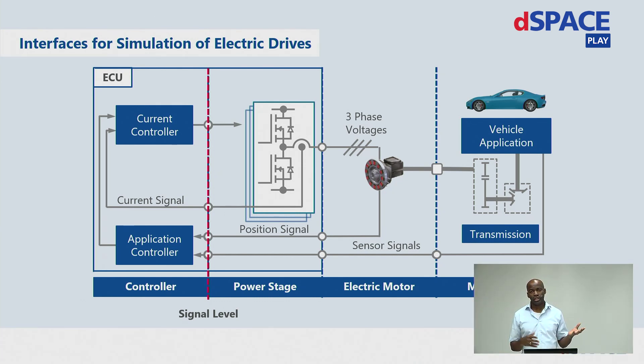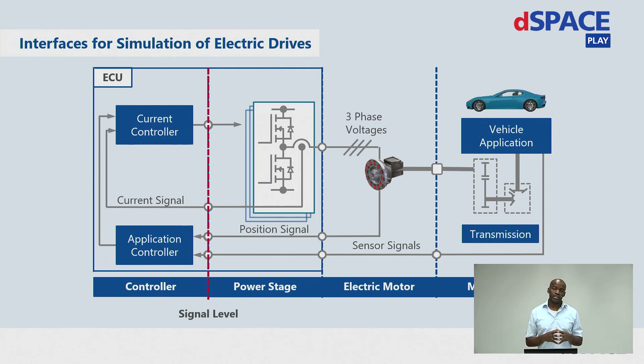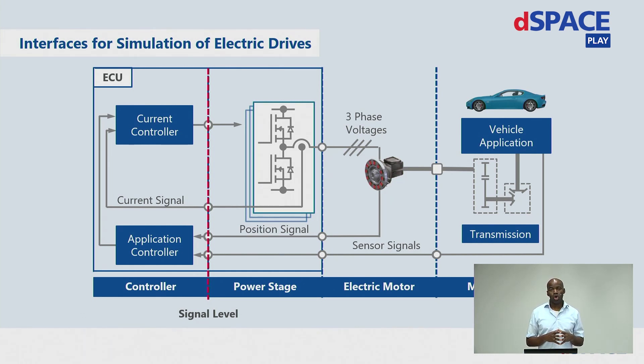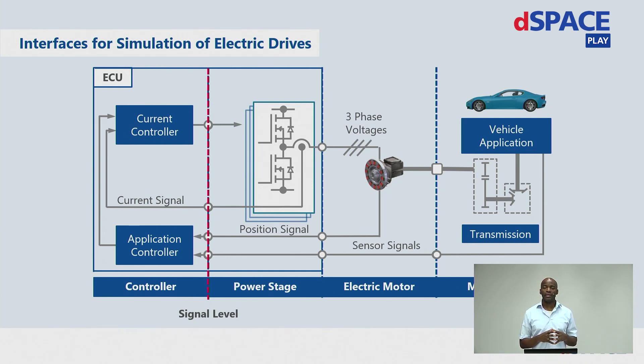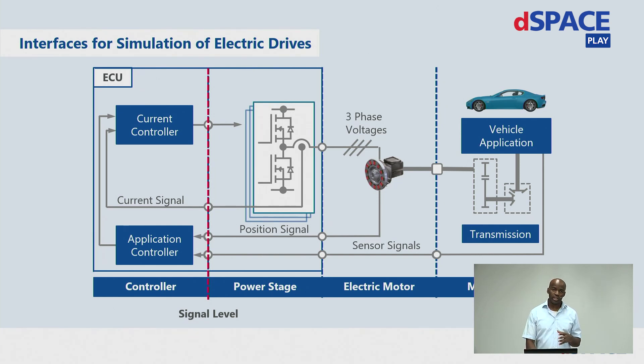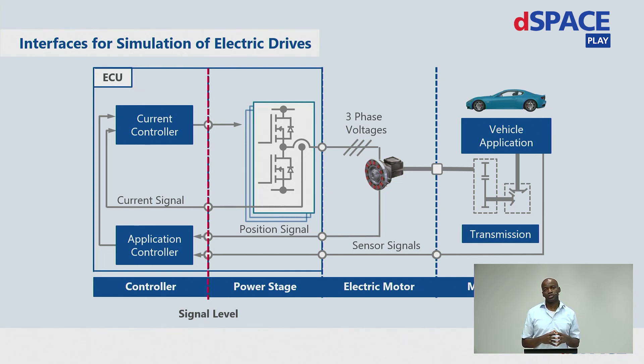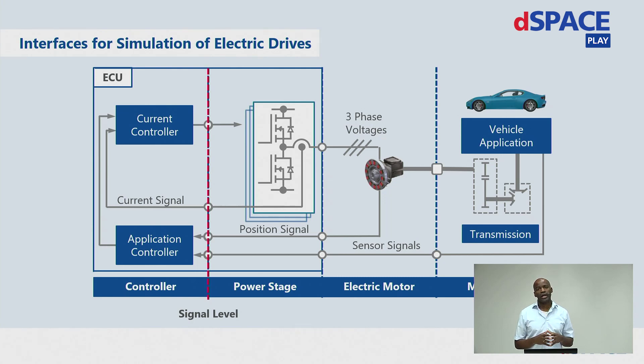For signal level and power level approach, a realistic simulation can be achieved only if the HIL system operates at a much higher sampling rate than the PWM carrier frequency of the device under test. Only with this high dynamic, it is possible to simulate high mechanical speeds and associated even higher electrical frequencies.